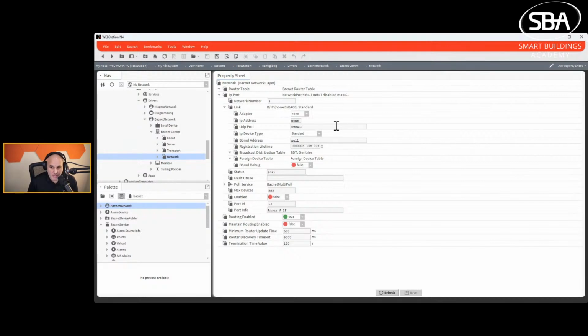The thing about a broadcast domain in a subnet is broadcasts can't propagate past their subnet boundaries. BACnet found a way to work around this by using BACnet broadcast management devices and broadcast distribution tables. So you have broadcast distribution tables, and that's a table for every BBMD, and then the BBMD propagates that broadcast, that who-is, I-am discovery message throughout the subnet.